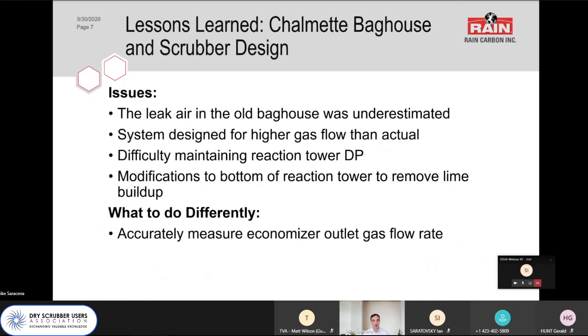Chalmette baghouse and scrubber design. So the Chalmette system was installed 3 to 4 years after the Lake Charles system was commissioned. At about the time when the Chalmette system was commissioned, we mostly had all of the problems with the Lake Charles system resolved. So it took us about 3 years to identify the source of all the corrosion problems, even understand that we had corrosion going on in the first place.